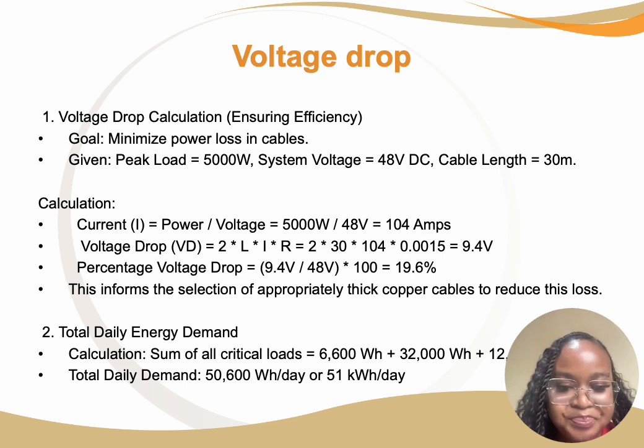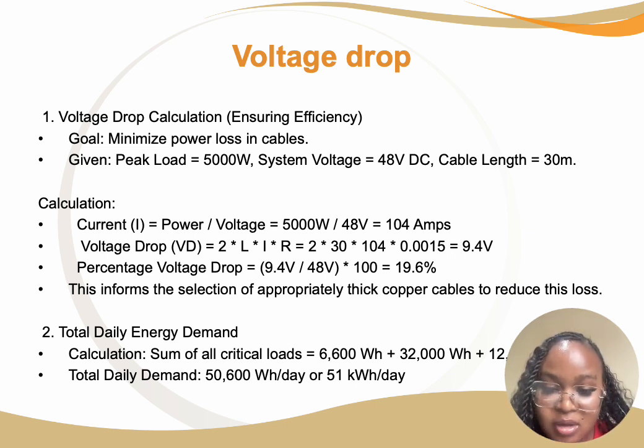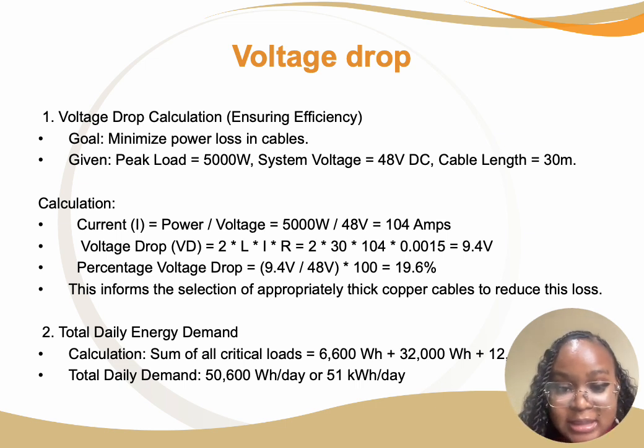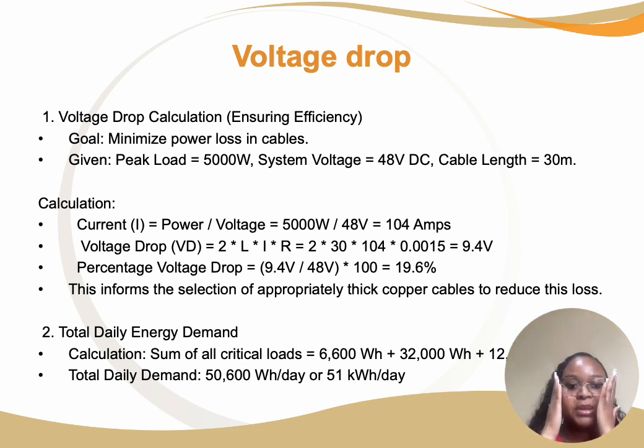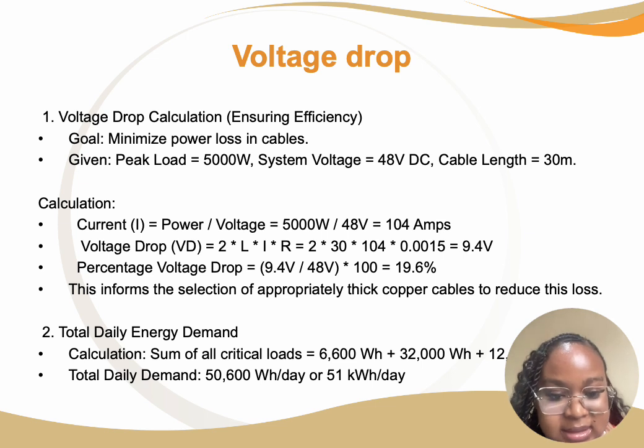We used our current, our resistance, our load to get our voltage drop. Then from there we calculated the percentage voltage drop, which was the 9.4 voltage drop that we got divided by 48, the system voltage, and then we multiplied it all by 100 to get the percentage of 19.6 percent. And then these calculations show the selection of appropriately thick copper cables to reduce power losses.